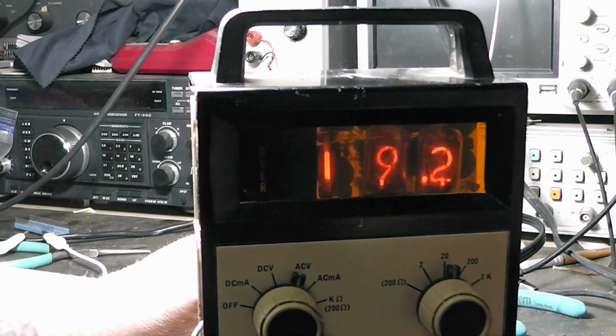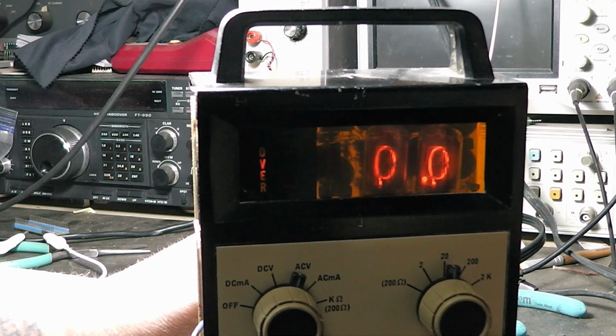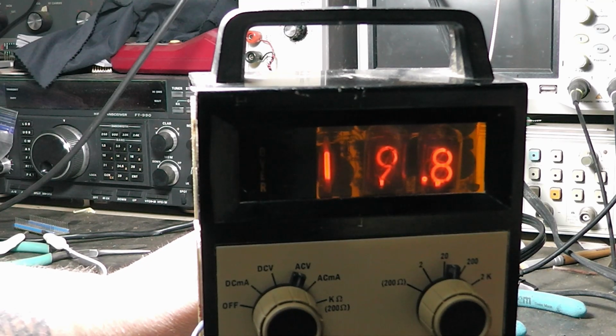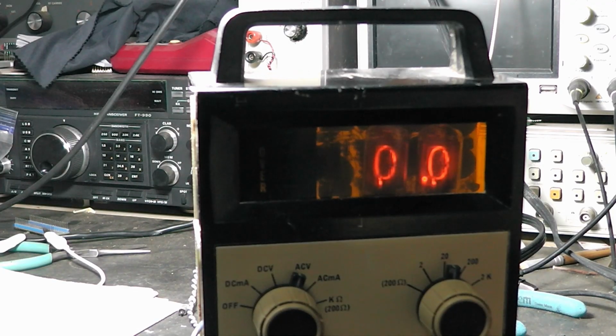So go to that AC and let it settle. That's pretty close right there. See how it's kind of jumping. If it's 0.98, 0.99, there it is. See, it's flickering. It's over and 00. That's where you want it. Okay, so that one's pretty close. The readout may vary between 19.9 and over 0.0 and over 0.1. A proper adjustment will read out over 0.0 most of the time.